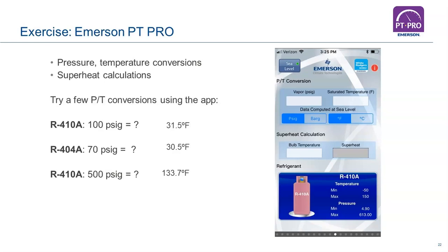When we're talking about superheat, we're talking about the temperature that's in the evaporator subtracted from what's leaving the evaporator. When we're talking about subcooling, we're talking about the temperature of the refrigerant inside the condenser subtracted from the temperature leaving the condenser. That's how simple that is. If we wanted to go farther, we had 31.5 here. If we took our temperature at our bulb leaving the evaporator, that bulb from our TXV, and we put 41.5 here, the difference would be 10 degrees superheat, okay?